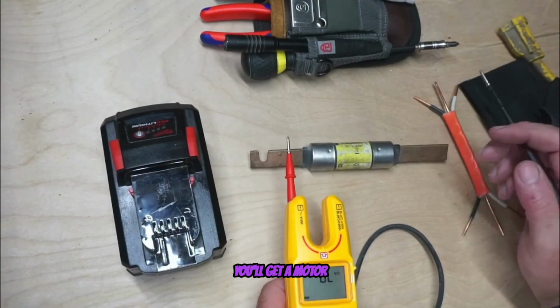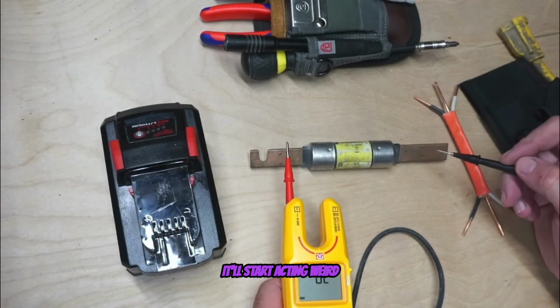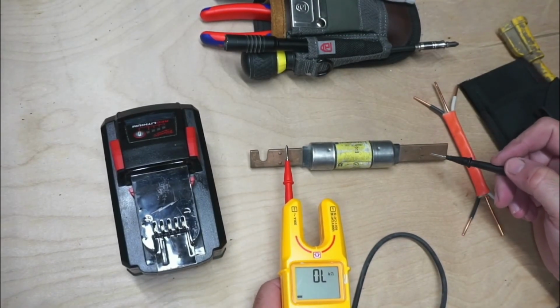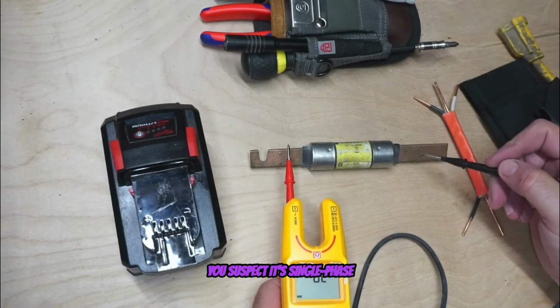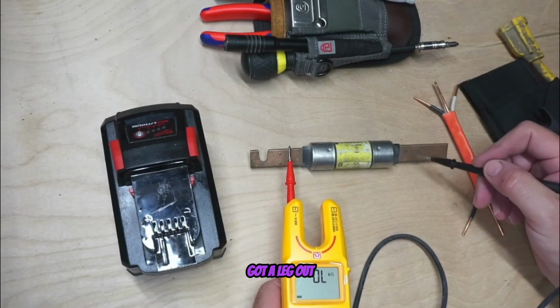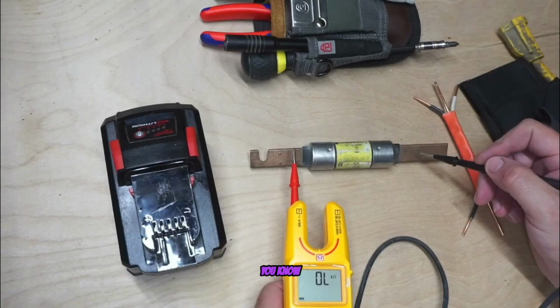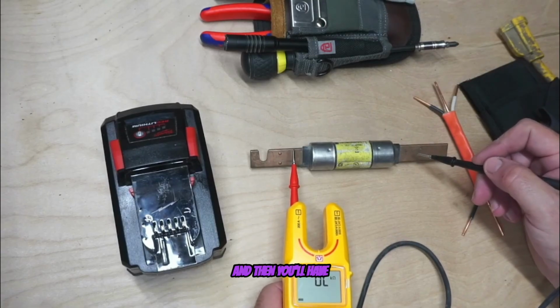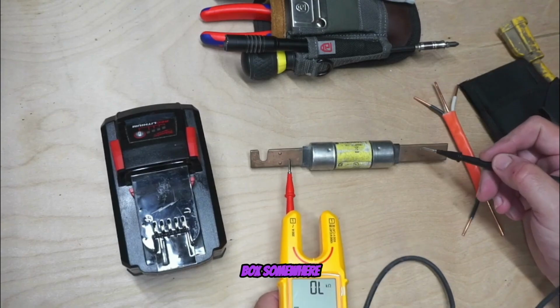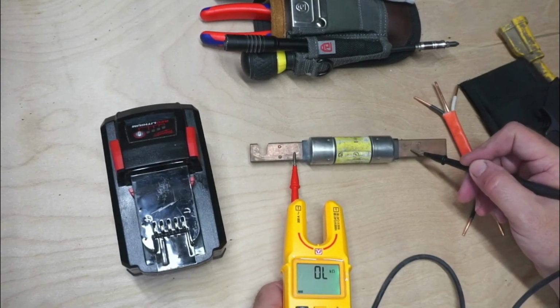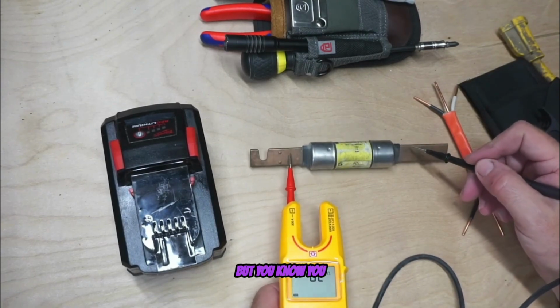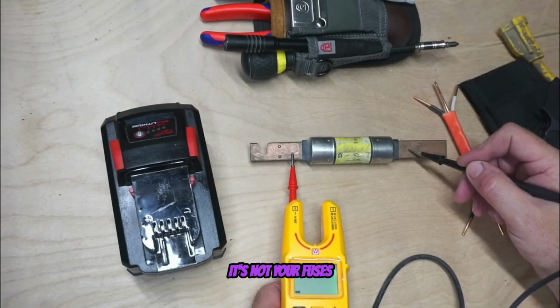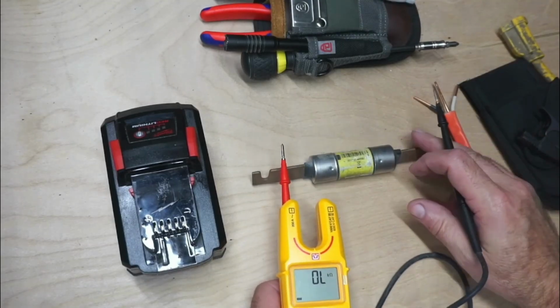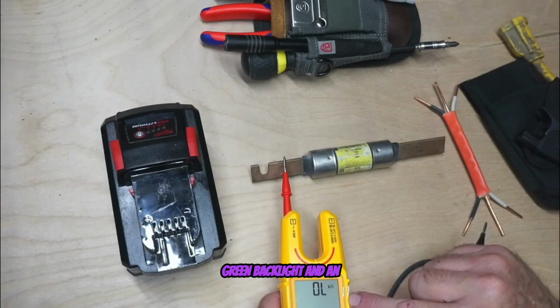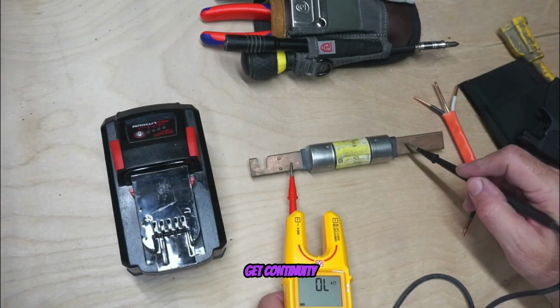You'll get a motor that's driving a machine, it'll start acting weird, sounding funny. You suspect it's single phasing, so you've probably got a leg out - each leg is driving the motor. Then you'll have 3 corresponding fuses in a disconnect box somewhere, so you go check them. That one's good, but you check all 3 and make sure it's not your fuses. Here's another feature - you get a little green backlight and an audible sound when you get continuity.